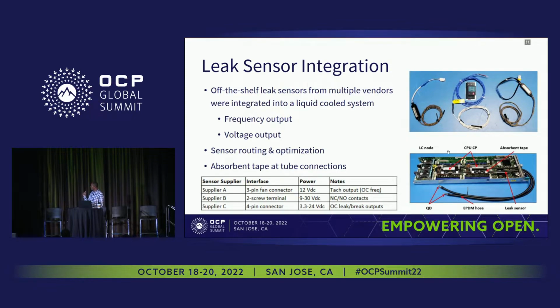Routing the sensors from the inlet side of the QD all the way to the outlet side of the QD, following the flow paths, and also the weakest link on this setup are the connectors. Normally, unless the tube is punctured, you're not going to get a leak from the tube. The weakest links are where those tubes are connected, whether it's on the cold plate or manifold or on the QDs. So at those locations, you use these absorbent tapes to wrap around, and the sooner we see a leak coming out, the sensors immediately will detect it. This would be a more efficient way of detecting a leak, as compared to laying down the sensor inside the chassis or somewhere.